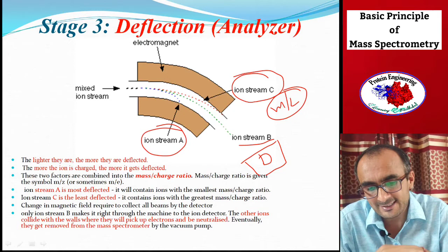So in fact, in order to collect all the beams in the sample, the magnetic field is changed from lowest to highest. Because the system, the mass spectrometer, is calibrated with known M by Z containing ions, from the magnetic field where a particular beam is being collected, its M by Z can be calculated. So from the analyzer, the M by Z of ions is calculated, and now this specific M by Z containing beam is detected by a detector in the last stage.